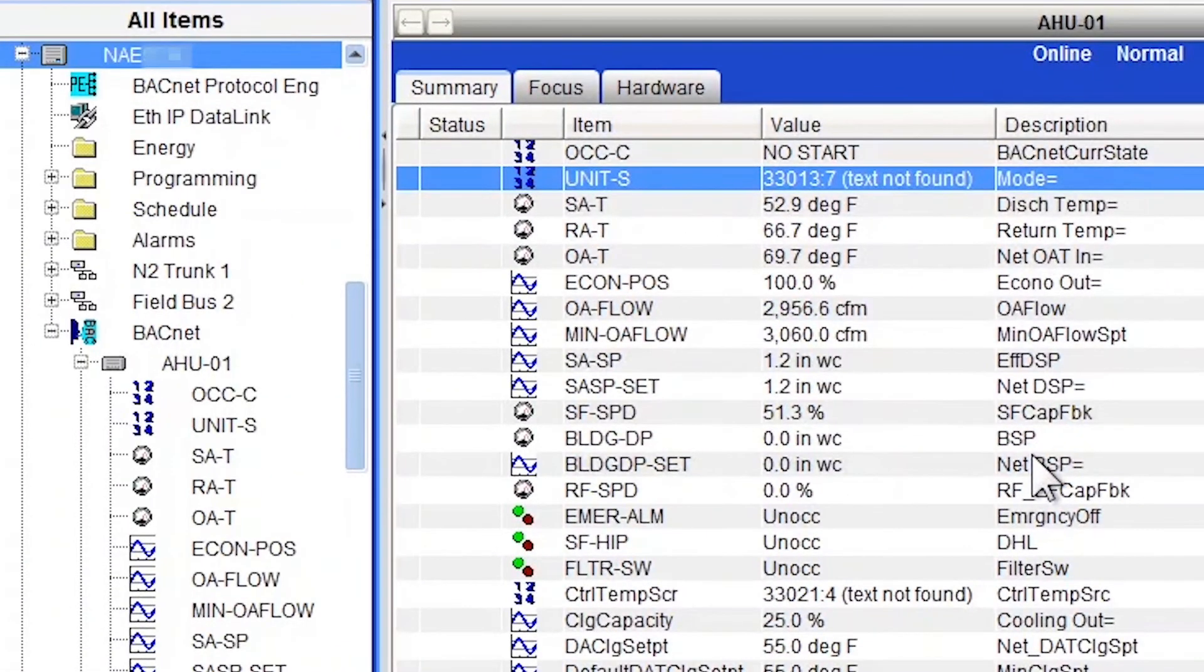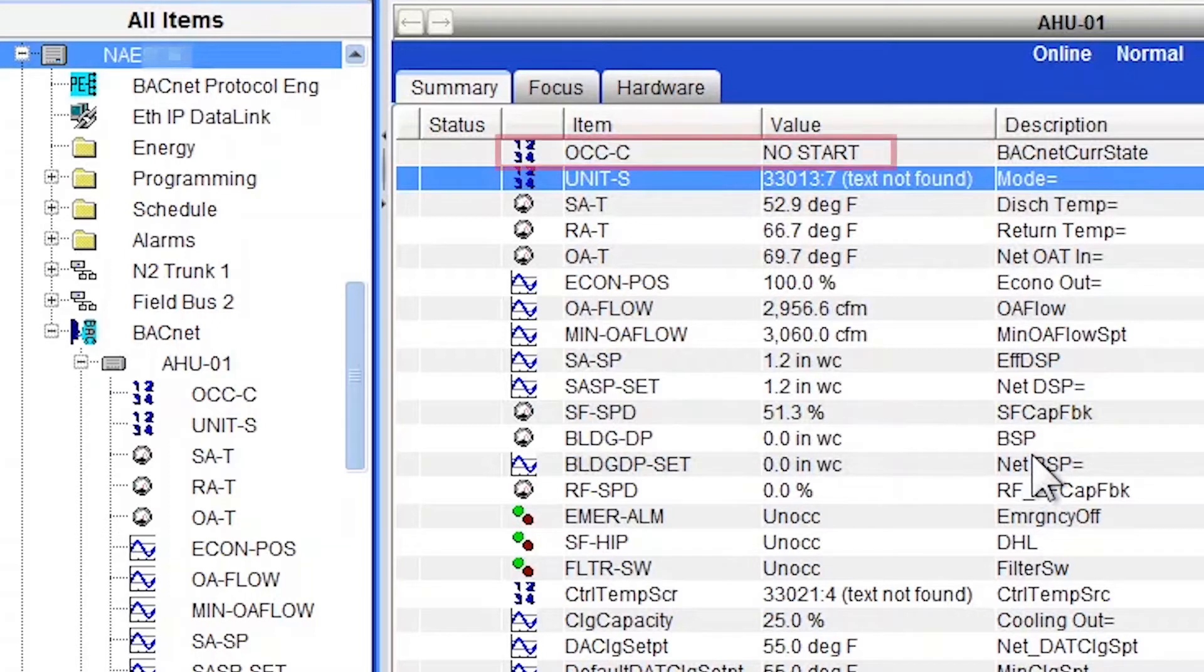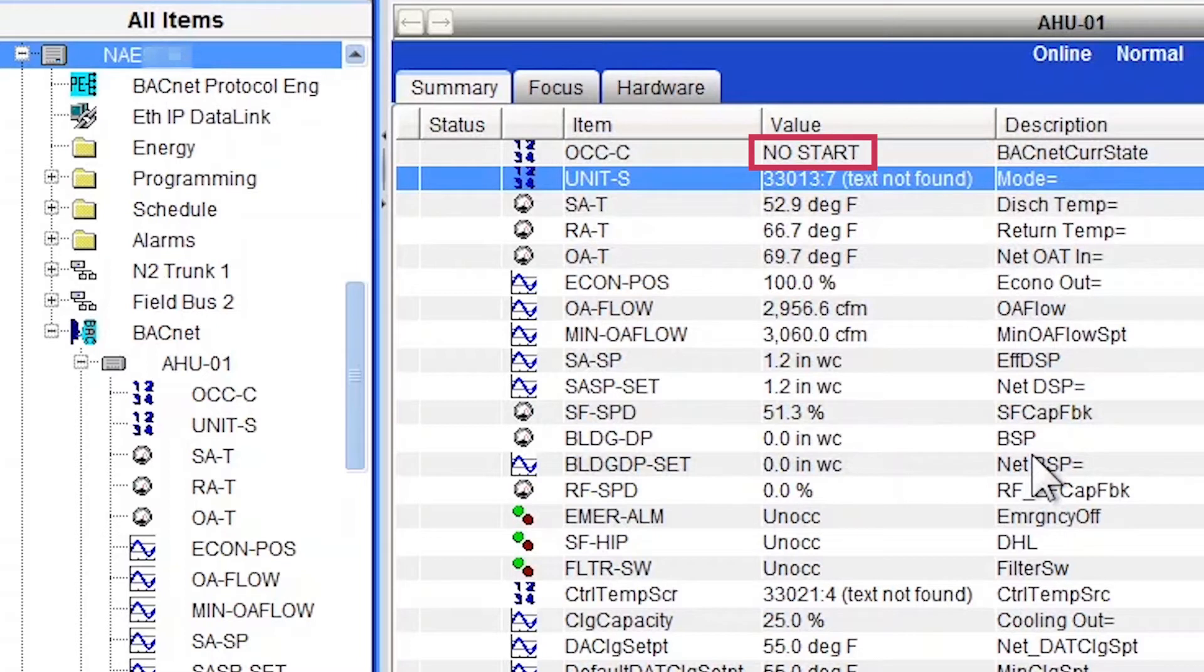Now, I don't know if you noticed, but there were a couple more points that got updated. The first one is OCC-C, Occupancy Command. Notice the units no start, which they don't make much sense. This should be something more like occupied, unoccupied, standby, something like that.